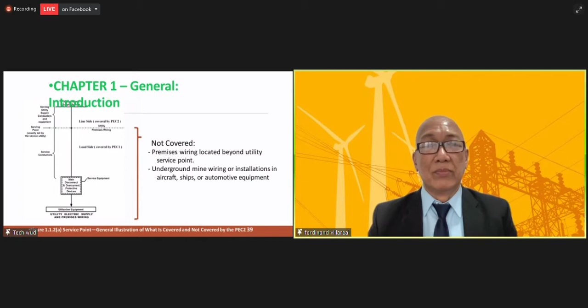To illustrate, here's the service point - up to here is the utility side, the colored wire is the utilization side already, with the exception of the metering equipment. The metering is not included - it's still part of the utility.